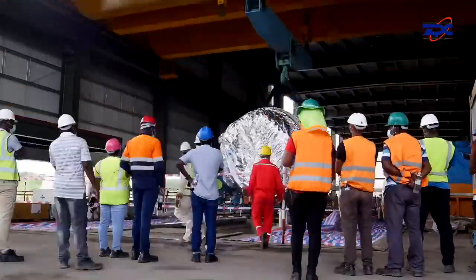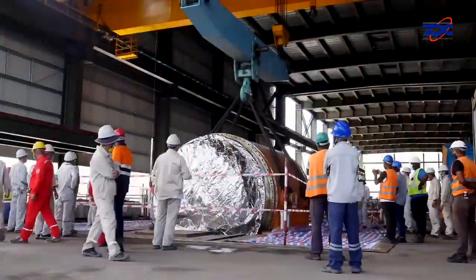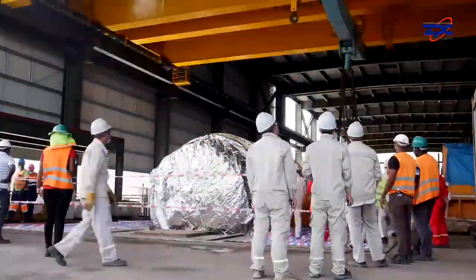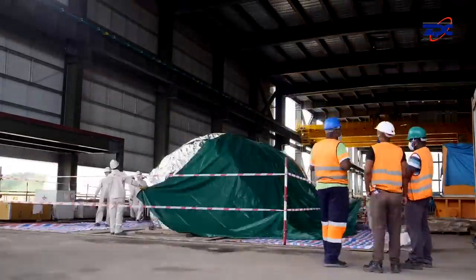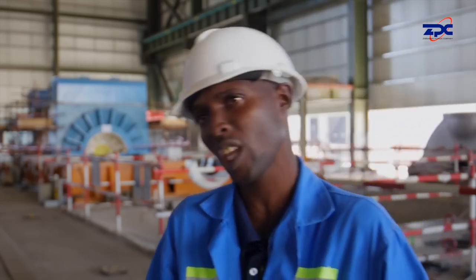The generators at Hwange expansion project, that is for Unit 7 and 8, are rated at 335 megawatts, and the generating voltage is 20 kV. At the stator terminal assembly, that's where we can now evacuate or transmit the generated power via the isolated phase buses to our generator step-up transformers, which are rated at 400 MVA, and the step-up voltage there is 20 kV, which is being stepped up to 400 kV.